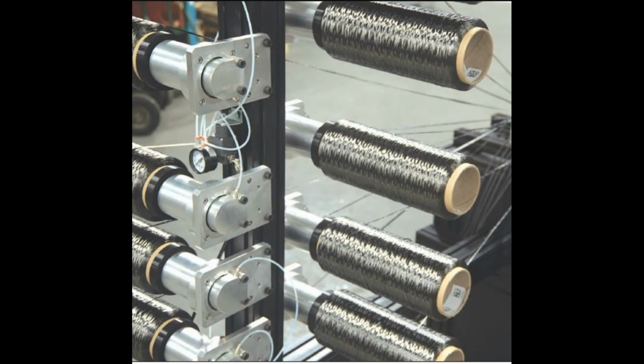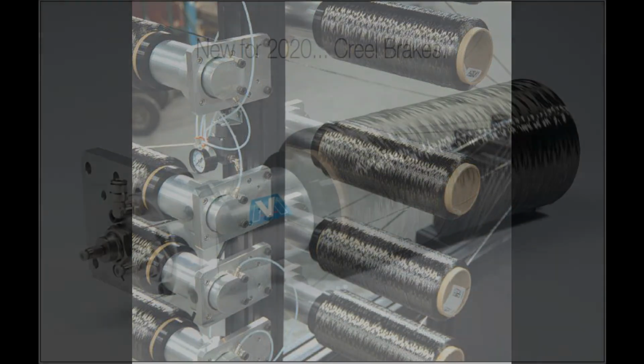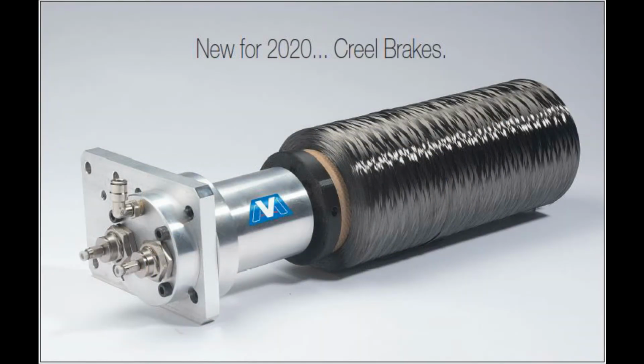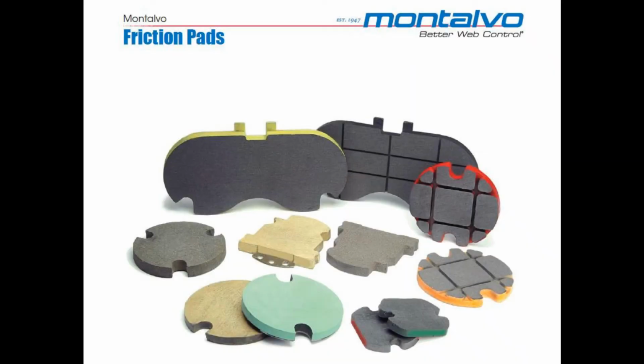The creel brakes are primarily comprised of a brake disc and friction pad. The amount of pressure the pad applies to the brake disc produces torque. As the controller changes the amount of air pressure based on the load cell's feedback, the friction pad alters its pressure to manage the desired torque required to maintain the tension set point. The Vanguard creel brake, like all of Montalvo's brakes, is available with friction pads manufactured from different materials to produce different torque ranges, depending on material and process requirements.